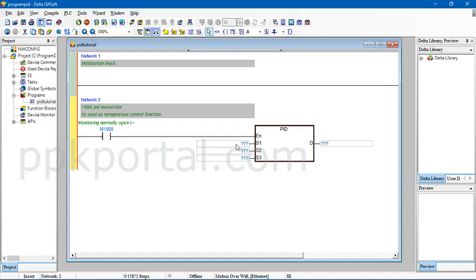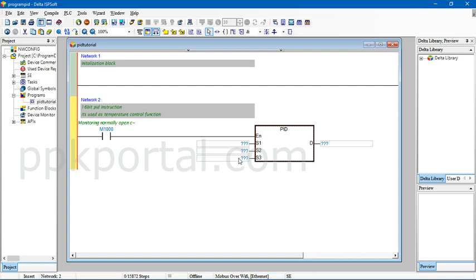When you are doing a program in real scanning case, you have to make sure that you are giving retentive memory for these PID settings, because once you tune the PID, the settings should remain there even if you turn off and on. You have to make sure that the register values for S3 are in the retentive range.